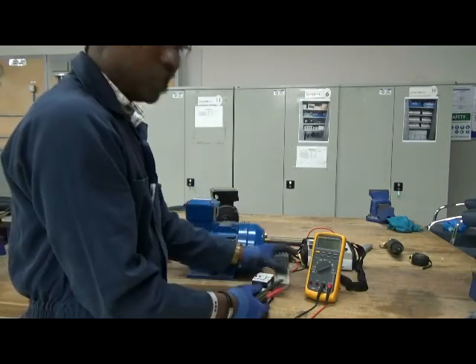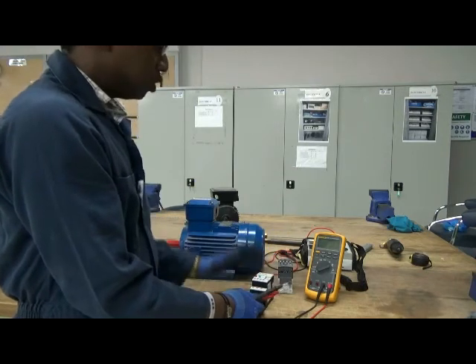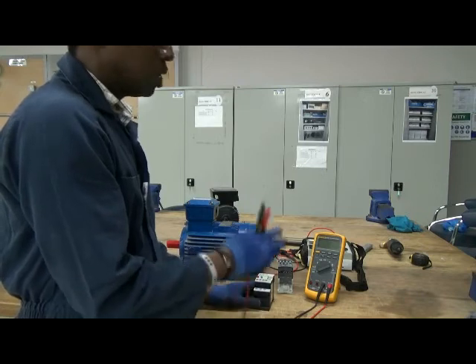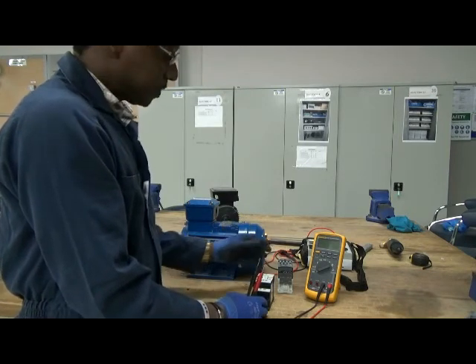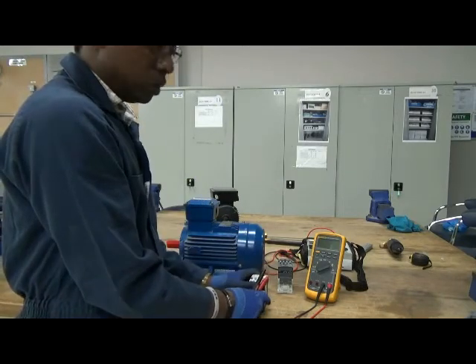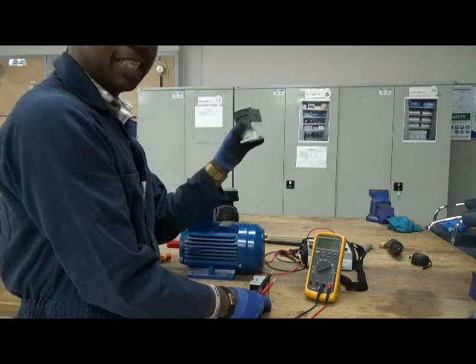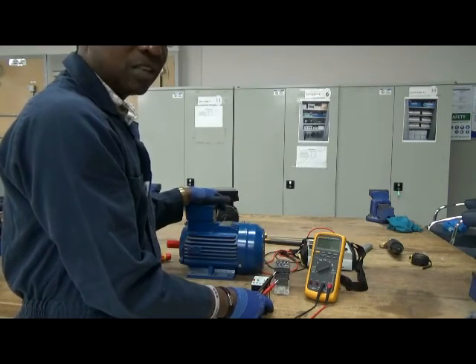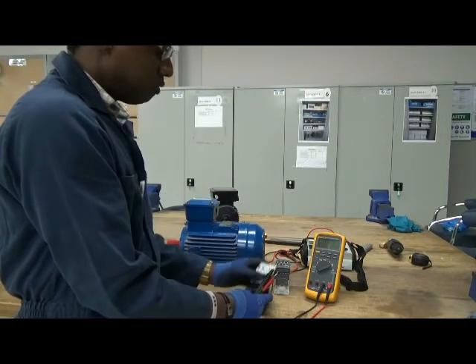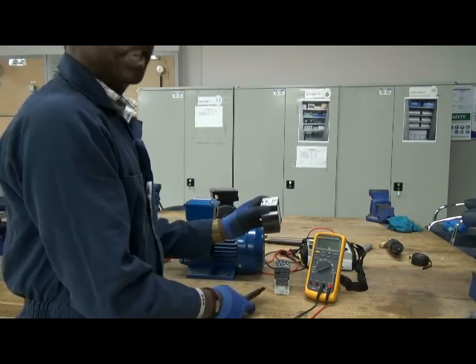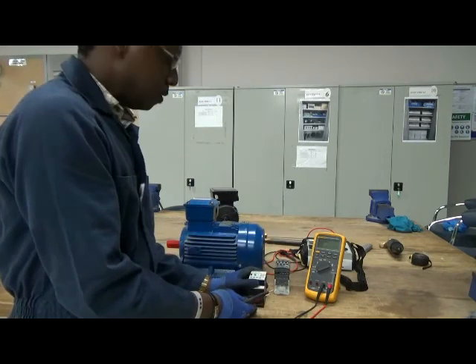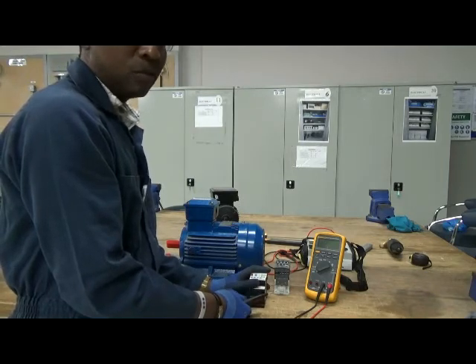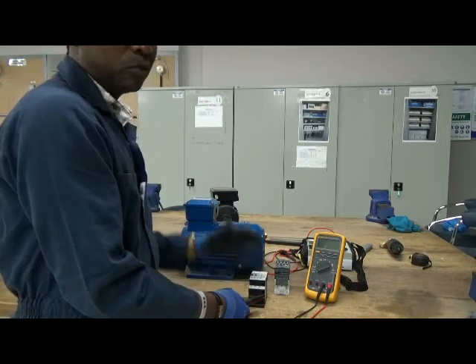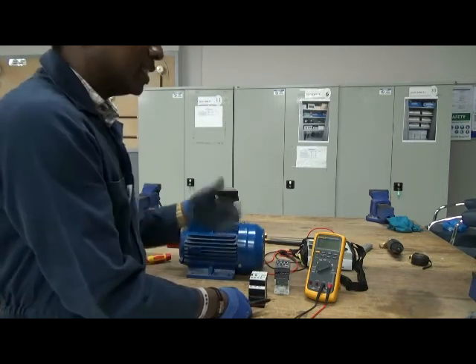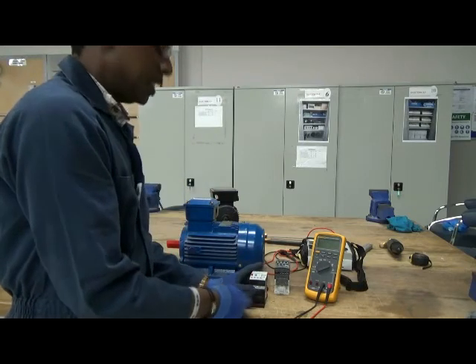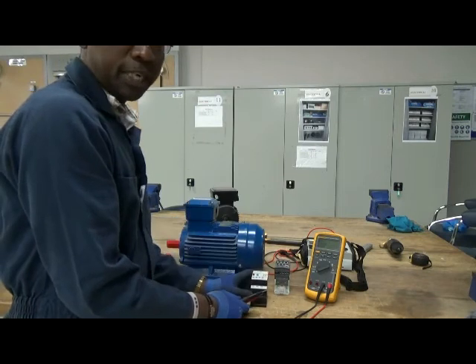So this happens automatically. You don't have to be there. The protection is done on its own. So the machine can be left running on its own for 24 hours or 48 hours. As soon as there's an overload, the overload unit will react and send a signal to the control circuit so that the contactor will get de-energized and stop the motor. The motor would not run until somebody comes and resets the overload. There's a resetting button on the overload here. We don't encourage people to just reset. First of all, qualified people want to know what has caused the trip, what caused the motor to stop. So they'll look for the cause of the overload, and once they've rectified it, they can reset the overload unit and start the machine again.